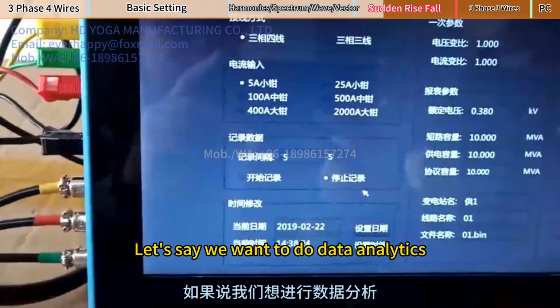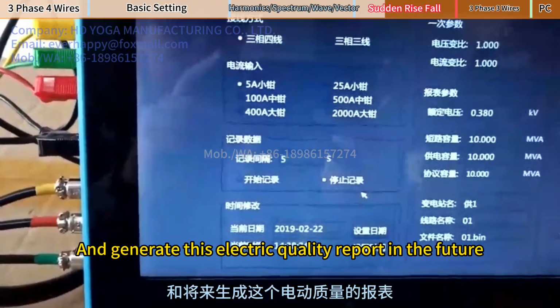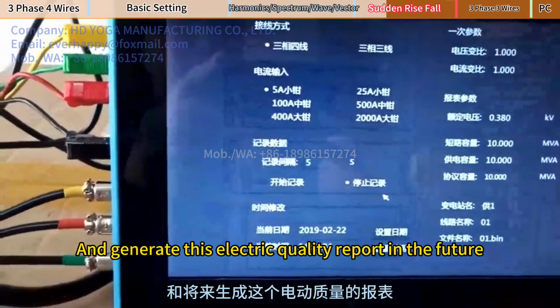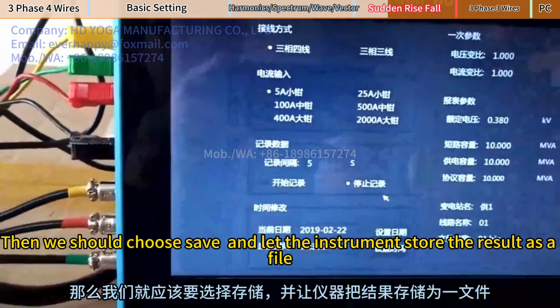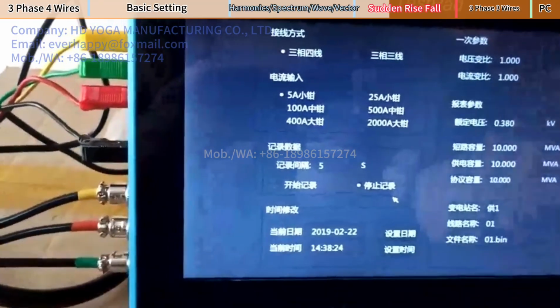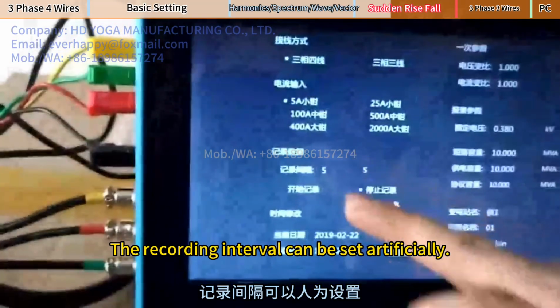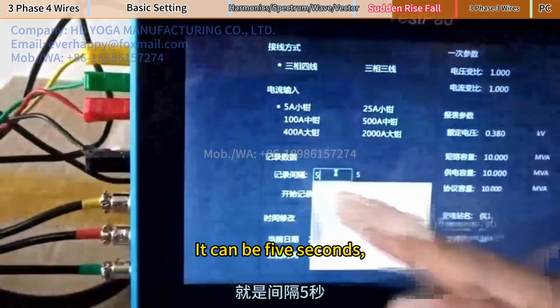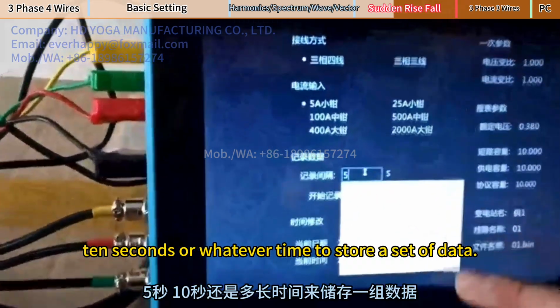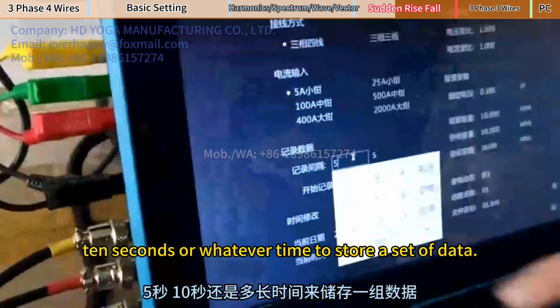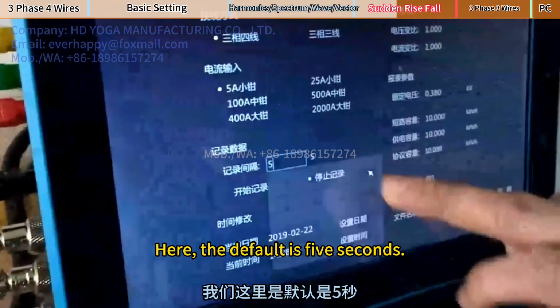Let's say we want to do data analytics and generate this electric quality report in the future. Then we should choose save and let the instrument store the result as a file. The recording interval can be set artificially. It can be 5 seconds, 10 seconds or whatever time to store a set of data. Here, the default is 5 seconds.